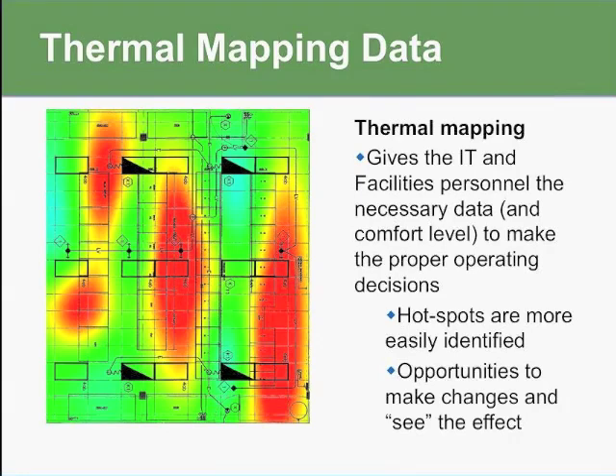As Nicole said, ASHRAE is saying that we can raise the temperature of the new equipment. You may still have some legacy hardware, IT equipment in the data center that could probably get reliable operation at a slightly higher temperature, but maybe not as high as the brand new IT equipment that you buy, whether it's a server, a storage array, a switch. So what this does, this gives you the data that both the IT people and the facility people can look at and get some kind of comfort to say, okay, I'm raising the temperature little by little.